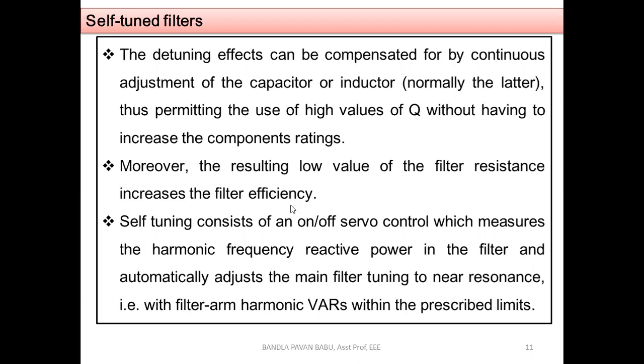Self-tuning consists of an on-off servo control which measures the harmonic frequency reactive power in the filter and automatically adjusts the main filter tuning to near resonance, keeping filter arm harmonic levels within prescribed limits. In earlier schemes, servo control performed the on-off tuning operations, whereas now controllable switches are preferred for this purpose.